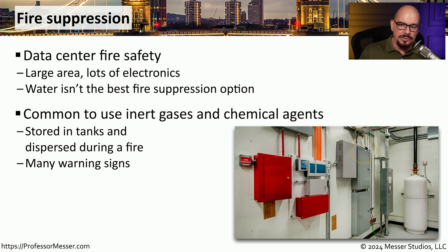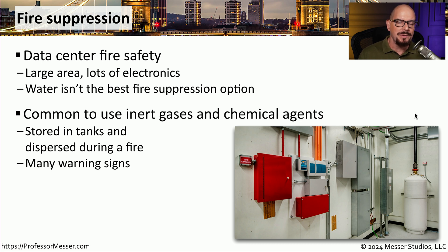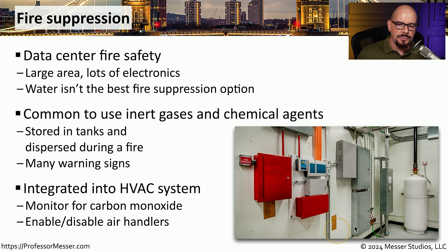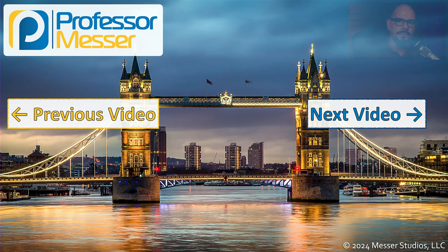If somebody pulls the fire alarm, all of those chemicals are dispersed throughout the entire data center. And although this may cause damage to the equipment, it will prevent a fire from spreading. You'll often see these fire suppression systems integrated with the existing HVAC, meaning that if a fire is detected, the HVAC system will shut down and prevent any type of oxygen from feeding that fire.